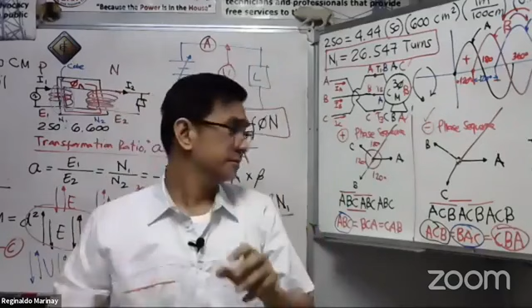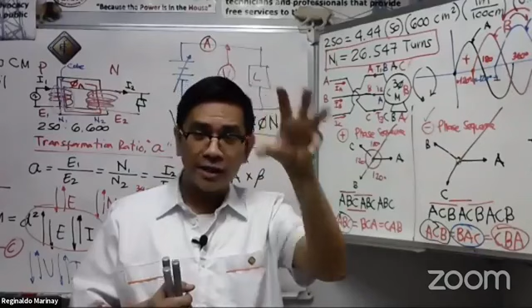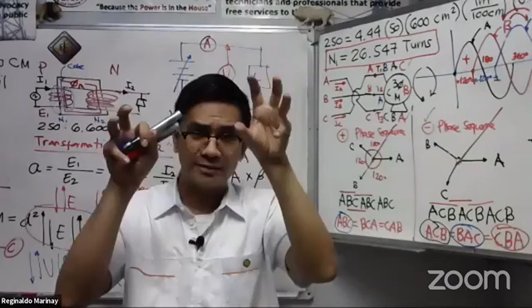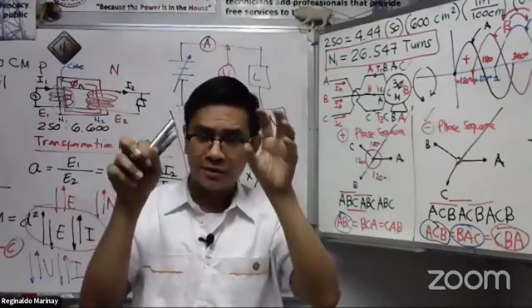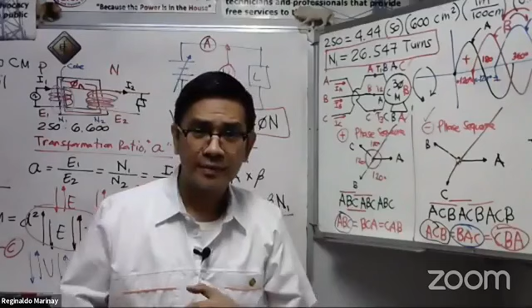There is an effect if this generator is already connected to the bus - this one is positive phase sequence, and you connect the negative phase sequence one. The effect on this generator may change the rotation of the shaft, and that may cause mechanical damage. That's one of the effects.